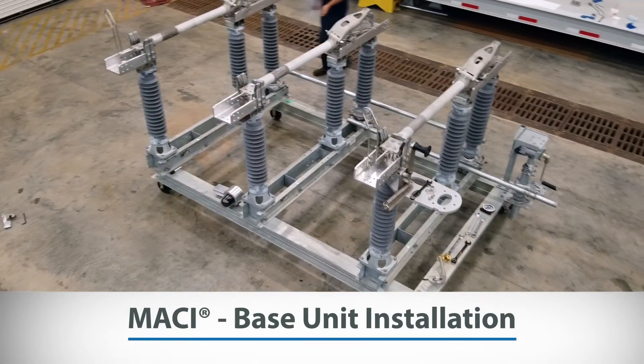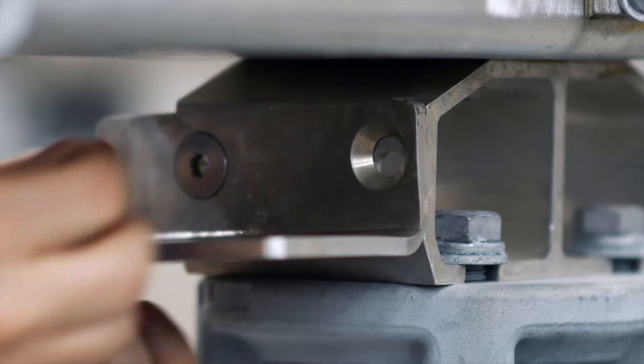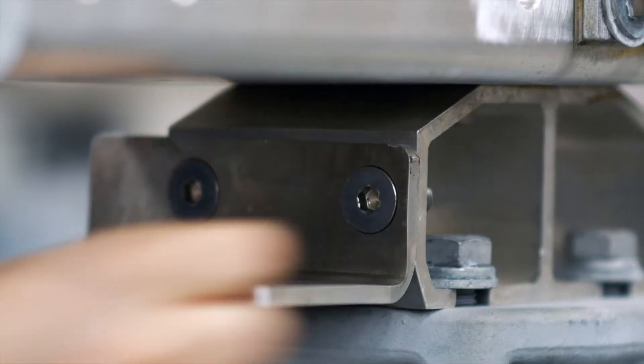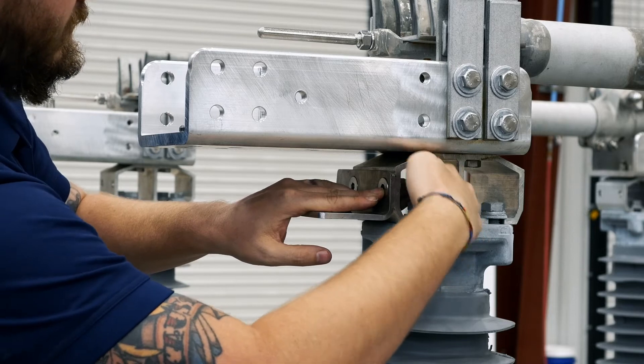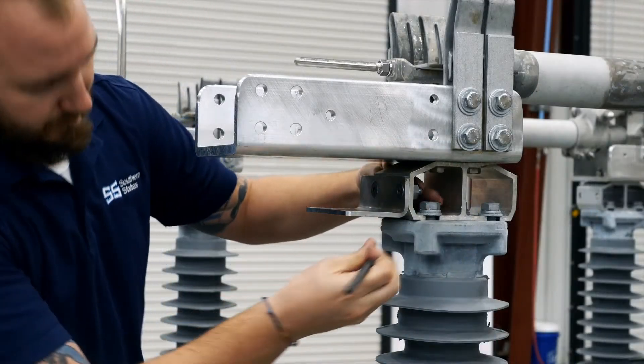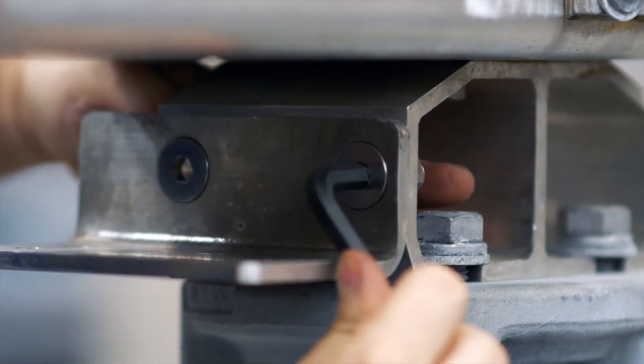MACI Base Unit Installation: Install the mounting bracket using the set screws and threaded extrusions underneath the blade jaw. A spacer may be required for some applications. Ensure your set screws are tightened using an allen wrench, which can be found with your supplied motor mechanism parts.